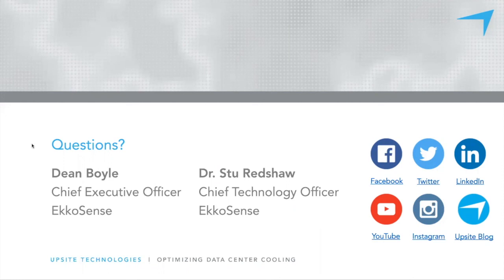But to give a more succinct answer, we would recommend, in fact we need, one sensor on the inlet on every single rack, or a significant portion, at least 80% of the racks. Also, we must be able to correlate for zones of influence with some of the deep machine learning algorithms. We also need the cooling duty sensors, but generally they are not cost prohibitive.